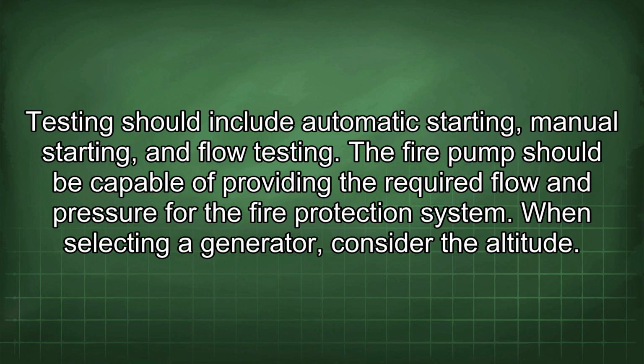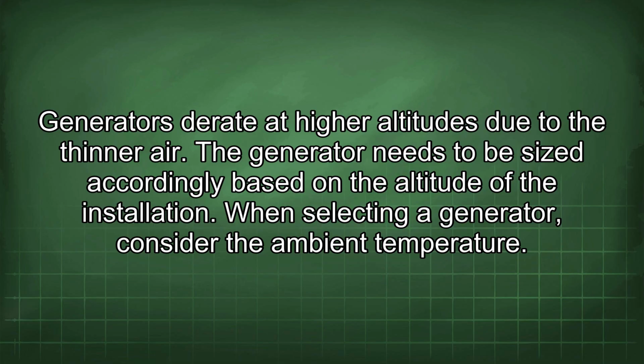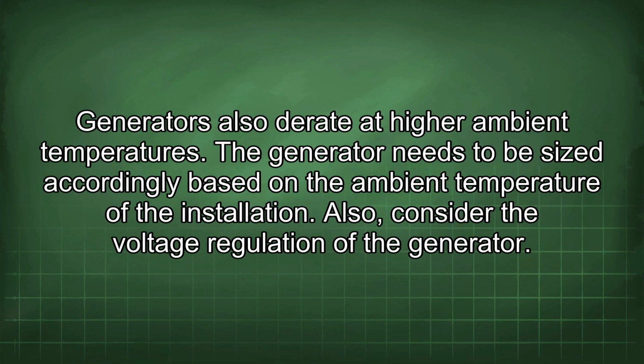When selecting a generator, consider the altitude. Generators derate at higher altitudes due to the thinner air. The generator needs to be sized accordingly based on the altitude of the installation. When selecting a generator, consider the ambient temperature. Generators also derate at higher ambient temperatures. The generator needs to be sized accordingly based on the ambient temperature of the installation.